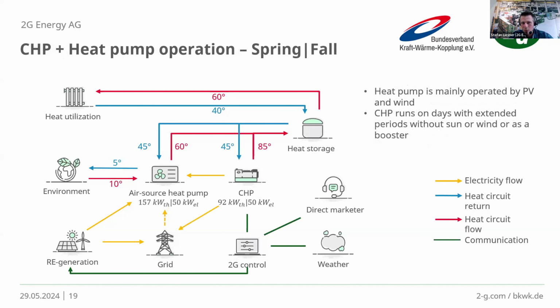When you compare that to spring and fall, it turns to a certain extent. In spring and fall it's getting colder, average only 10 degrees, and the backflow temperature only 40 degrees. So there are more and more times where you need the heat, and in these times the CHP can even serve as a kind of booster. You see a classic air source heat pump with only 60 degrees flow temperature, and then a booster with the CHP with a flow temperature of 85 degrees. As I was already saying earlier, in the end it's a matter of technical and smart combination. And this is what's being done by companies like Sokratherm, 2G or Kraftwerke, or whoever, members of B.KWK.